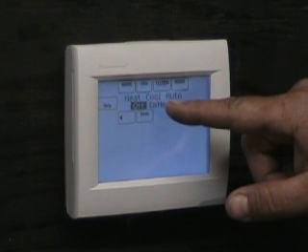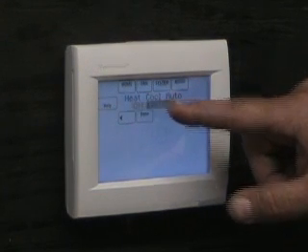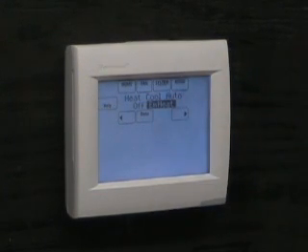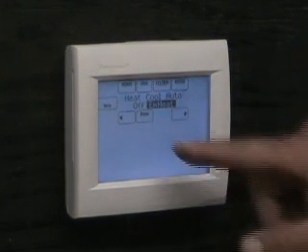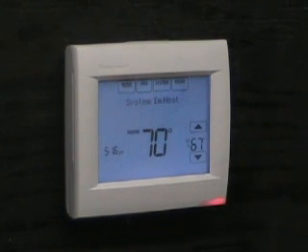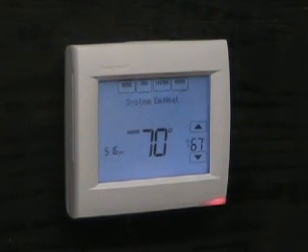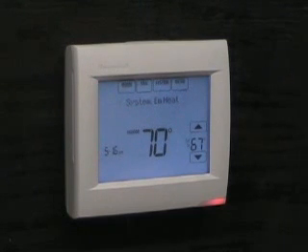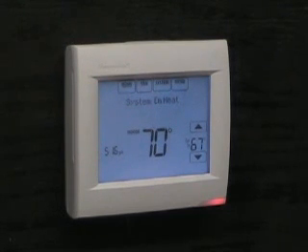If you have a heat pump in emergency heat mode, the heat setting is shown, but the thermostat will bypass the normal first stage compressor heating and will use the backup heating as the only source of heating.